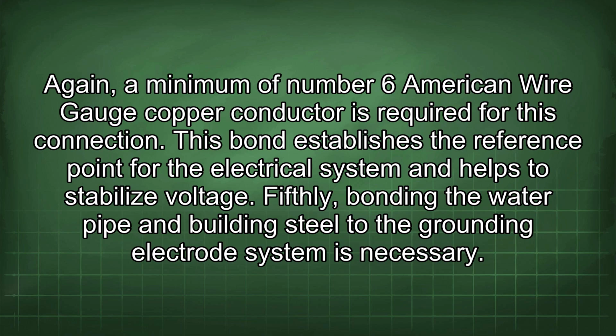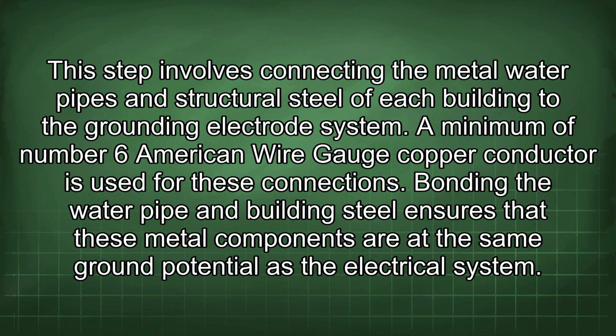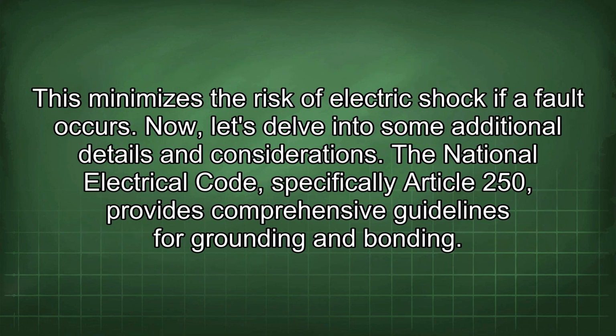Fifthly, bonding the water pipe and building steel to the grounding electrode system is necessary. This step involves connecting the metal water pipe and structural steel of each building to the grounding electrode system. A minimum of number 6 American wire gauge copper conductor is used for these connections. Bonding the water pipe and building steel ensures that these metal components are at the same ground potential as the electrical system. This minimizes the risk of electric shock if a fault occurs.